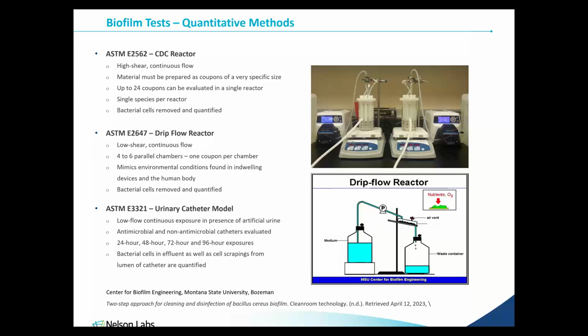An additional biofilm method is available that specifically evaluates prevention of Escherichia coli biofilm in antimicrobial urinary catheters. This method is ASTM E3321. In brief, both antimicrobial and non-antimicrobial catheters are exposed to an artificial urine medium and then contaminated with E. coli. During the entire test, the biofilm is exposed to a continuous flow of artificial urine through the catheter.